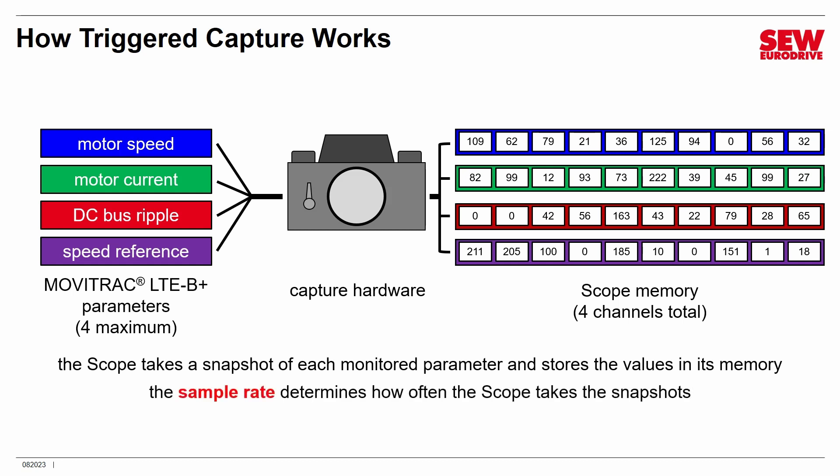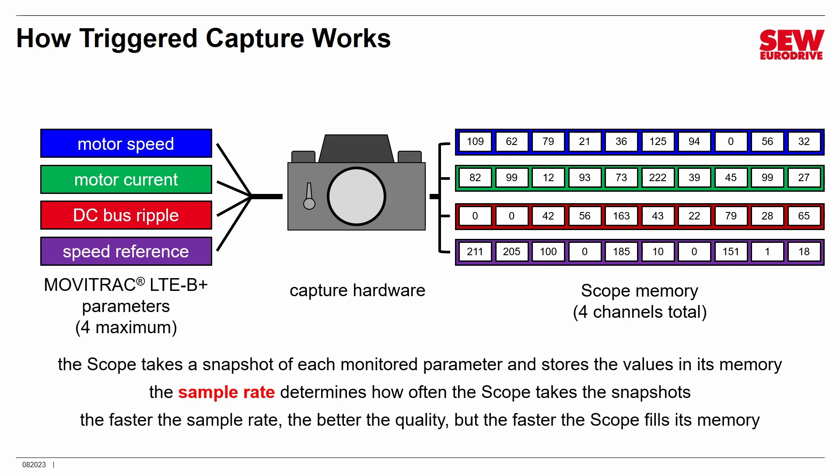There is something called the sample rate that determines how often the scope takes snapshots. You can set it so it's taking snapshots very rapidly — maybe every 10 milliseconds — or you could set it really slow, maybe just a few samples per second. The sample rate will be largely determined by what you're looking for. Here's the key idea: the faster the sample rate, the better the quality of the trace, but also the faster the scope fills its memory. A very fast sample rate will fill up memory quickly but give you a very high-quality trace. A slower sample rate will stretch out the memory longer, but the trace will be poorer. Picking the sample rate is something of an art — you have to often compromise between quality and how long you can capture data.